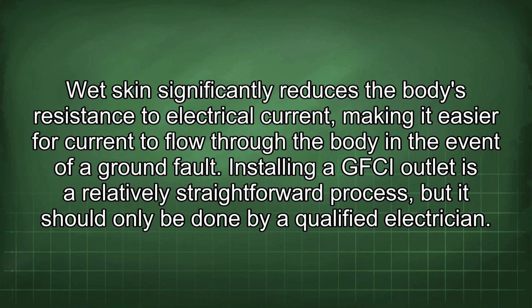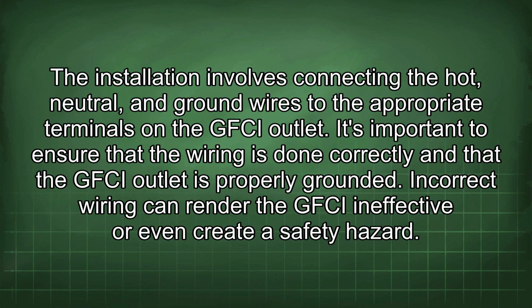Installing a GFCI outlet is a relatively straightforward process, but it should only be done by a qualified electrician. The installation involves connecting the hot, neutral, and ground wires to the appropriate terminals on the GFCI outlet. It's important to ensure that the wiring is done correctly and that the GFCI outlet is properly grounded. Incorrect wiring can render the GFCI ineffective or even create a safety hazard.